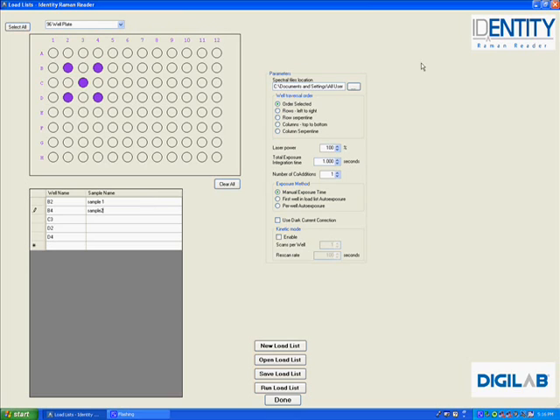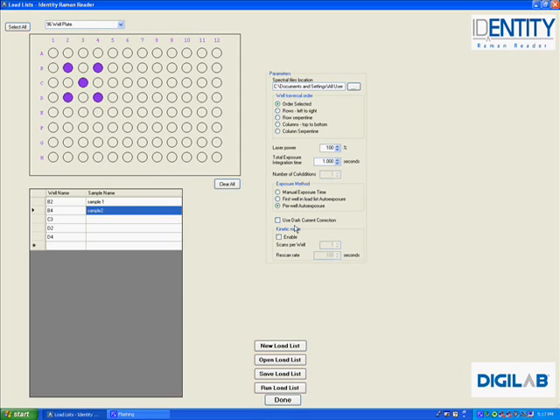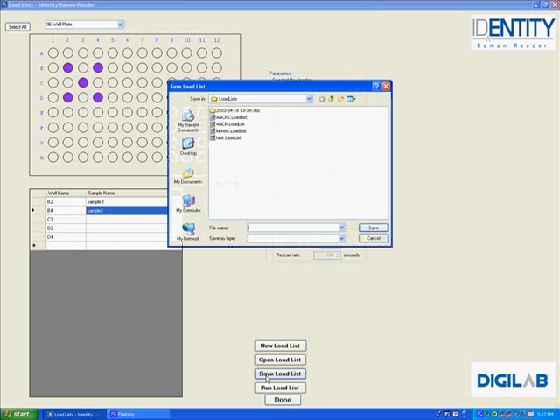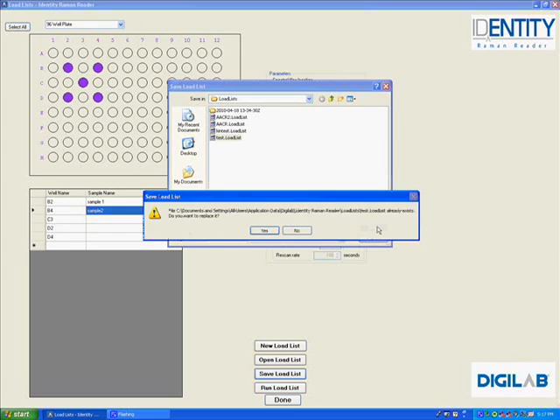On the right, we have our controls for setting the spectrometer acquisition mode, which allows us to set this up and then save a plate map view, which then would be set and usable by any technician going forward.